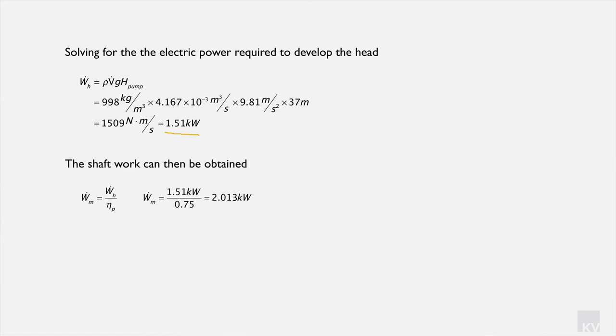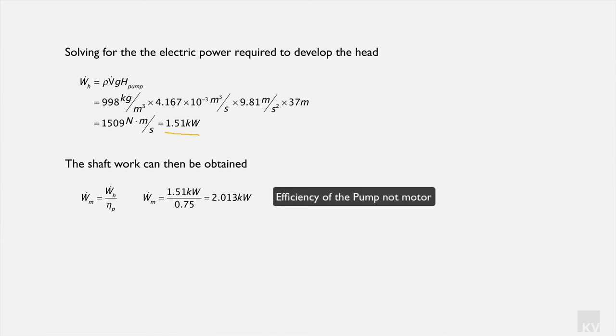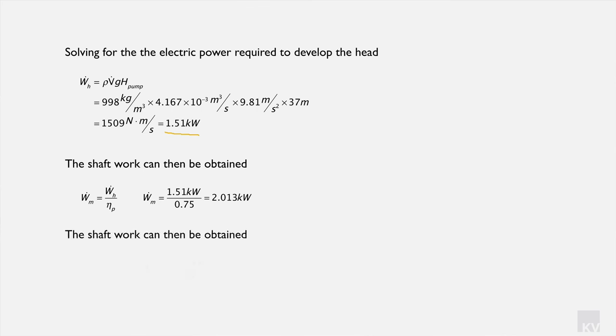The shaft work is found from: rate of work of the motor = rate of work required to develop the head divided by pump efficiency. Substituting 1.51 kW and the pump efficiency, the work required by the motor is 2.013 kilowatts. Finally, the electric power is the motor work divided by the motor efficiency: 2.013 kW ÷ 0.85, giving approximately 2.4 kilowatts of electric power required.